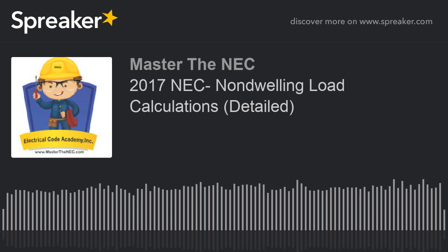Now, 220.56 is a way for us to apply demand factors to the actual nameplates that are on these kitchen appliances. Okay? So, if I've got two appliances, and that's all I've got in this kitchen, or two pieces of kitchen equipment, then I'm going to have to take them at 100%. I don't get any demand. I take them at 100%. That's what the table says in 220.56. It is what it is. Okay? You take the full value.